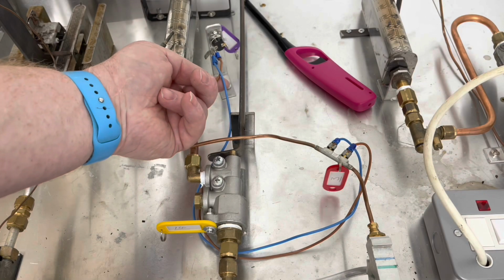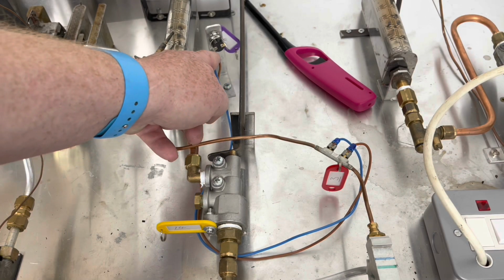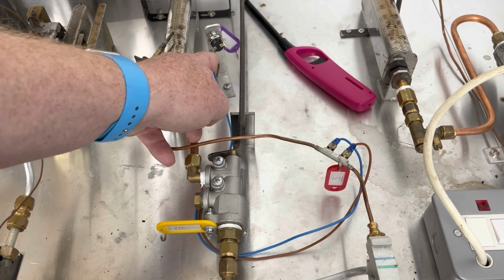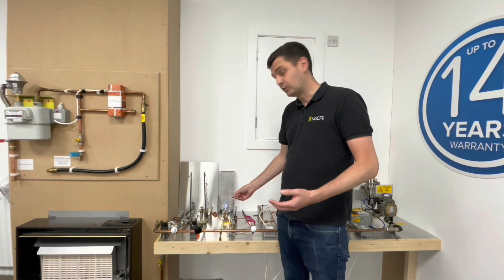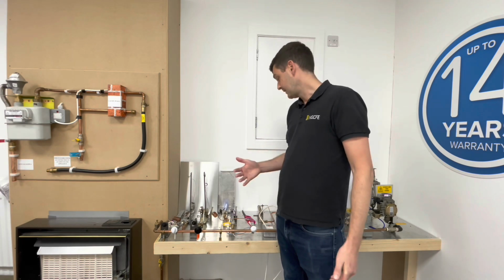You may notice that we've got the overheat stat bridged out on this. That's because this overheat stat is faulty, it's actually tripped. So all we've done is we've manually overridden it by putting the connections on the same spade.